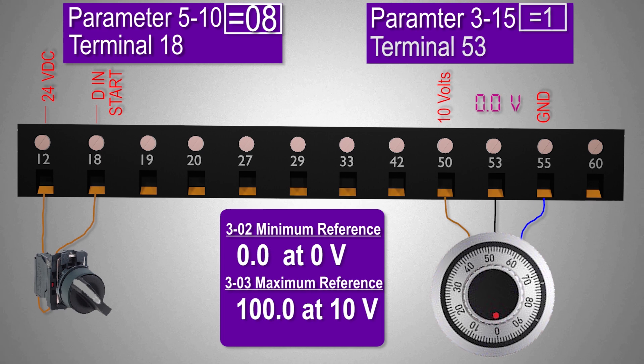For this example I set 0 Hertz speed at 0 volt analog input signal and 100 Hertz at 10 volts analog input signal.